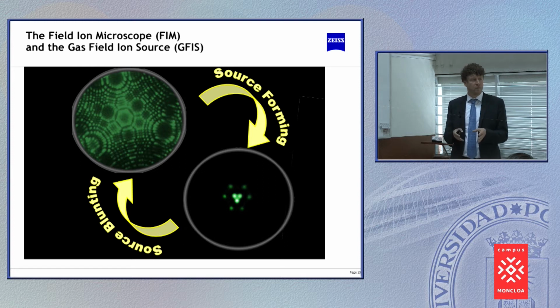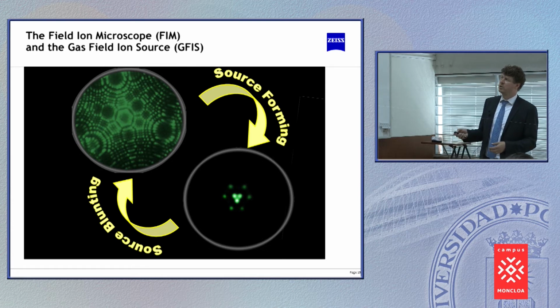So the lifetime of one tip is just around 1 week. So it depends on your work. When you do nothing, then it's of course longer. But we can sharpen this, and this takes some minutes. So there's an automatic procedure to do this.